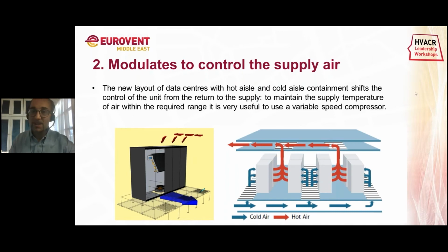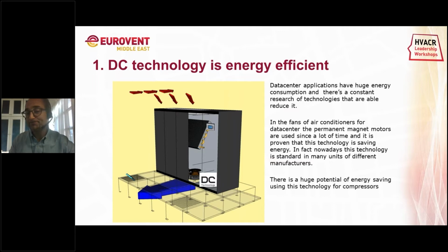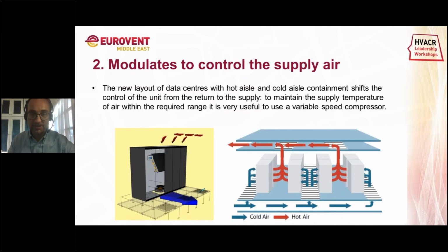Sorry, I need to go back one slide. So it's well known, and there is a great potential for compressors. Second reason is that they can modulate. As it was introduced in the previous presentation, now with a cold aisle and a hot aisle containment, it's becoming paramount to have the possibility to control the supply air temperature. It is quite difficult to control with an on-off compressor. With a modulating one, it is possible to achieve a better control and a better stability of supply air temperature.